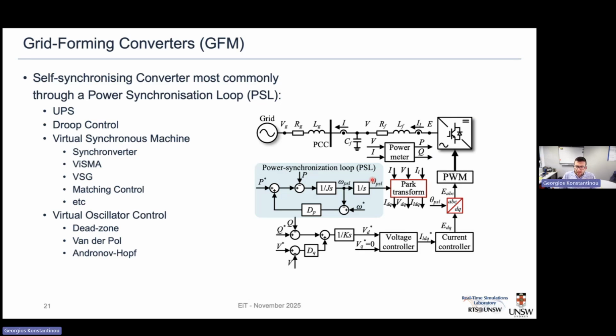In order to generate this grid forming control, we are looking at an internal way of synchronizing converters to the network. That's what we refer to as a self-synchronizing mechanism, which most commonly, when you hear of grid forming control, in the majority of cases refers to a synchronization through a power loop.